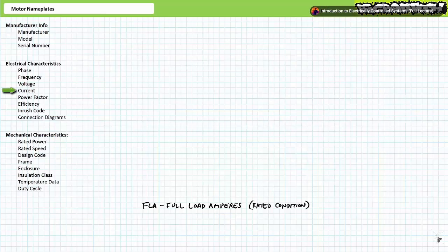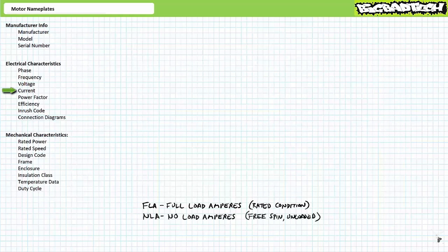Some motor nameplates include accessory information about current. If a nameplate includes the accessory entry NLA, this is the no load amps, drawn while the motor is free spinning and experiences no oppositional torque. If a nameplate includes the accessory entry LRA, which stands for locked rotor amperes, this is the inrush current drawn when the motor is first started at a standstill or locked rotor condition.